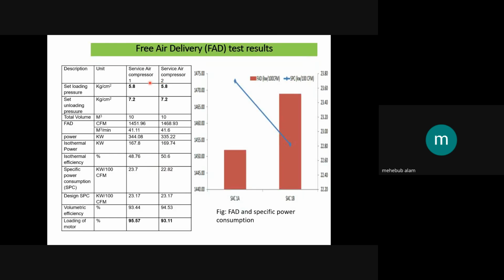After completing the data collection, the different parameters are shown here, like the pressure, set loading pressure, set unloading pressure, total volume, FAD. Here two parameters are important. The set pressure for service compressor 1 and service compressor 2 was 5.8 kg per centimeter square, and the unloading pressure was 7.2 kg per centimeter square. In the service air compressor, the discharge pressure was actually high, and this high discharge pressure was causing energy loss, which is not expected.